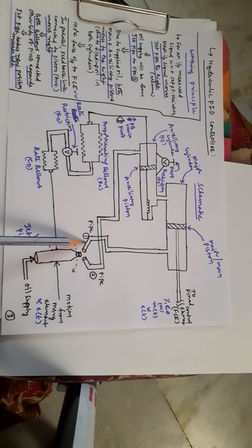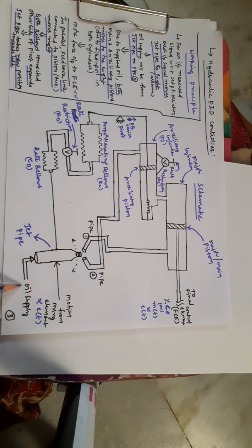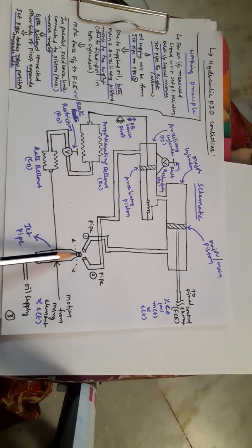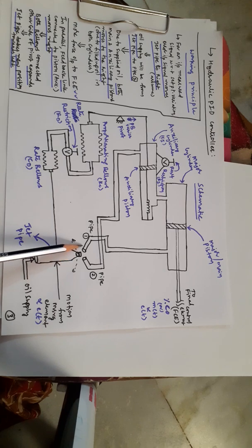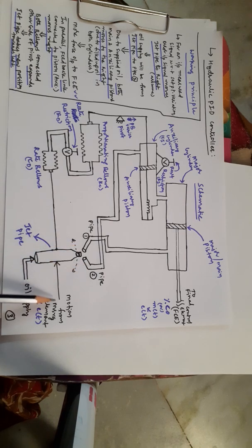The auxiliary piston is connected to pipe 2 and the main piston is connected to pipe 1. Pipe 1 is connected to the main cylinder; pipe 2 is connected to the auxiliary cylinder. We also have a jet pipe — the hydraulic fluid used is oil. The oil supply is sent through this jet pipe. When the jet pipe moves to the left it connects to pipe 1; when it moves to the right it connects to pipe 2.